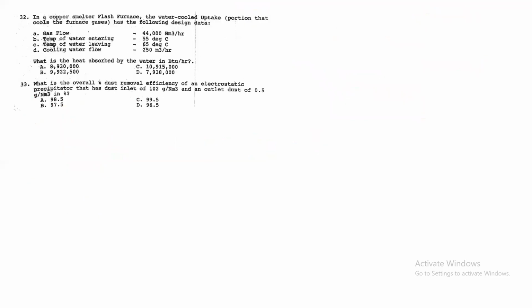So, next, 32. In a copper smelter flash furnace, the water-cooled uptake has the following design data. What is the heat absorbed by the water in BTU per hour? So, paano itong 32? Heat absorbed by the water. So, para makuha natin, Q is equal to mC delta T. Ganyan lang siya kadali, guys. So, ilan yung mass natin? So, 250 meter cube per hour.